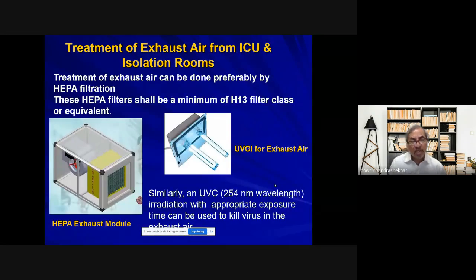Now, after COVID, treatment of exhaust air has also become very important, and it is preferably done by HEPA filtration. This HEPA filter shall be a minimum of H13 filter class or equivalent. So you can see that the air, before it is thrown out, passes through a HEPA filter, so that the environment doesn't face a problem when air is released from a COVID hospital.